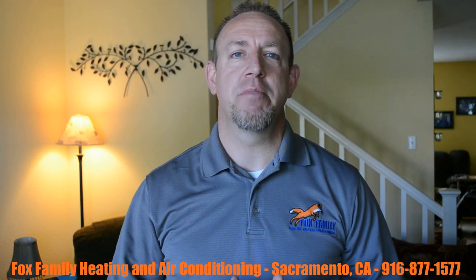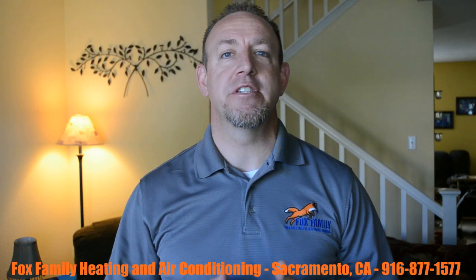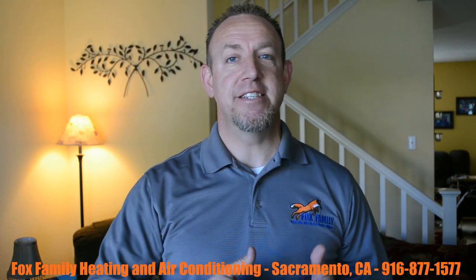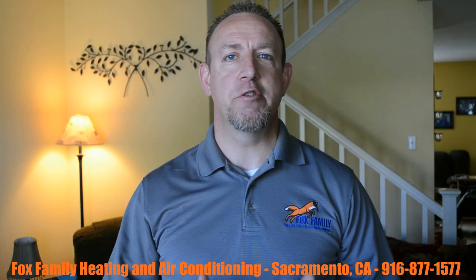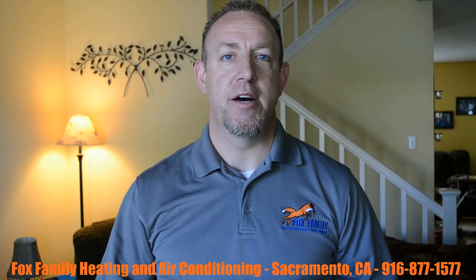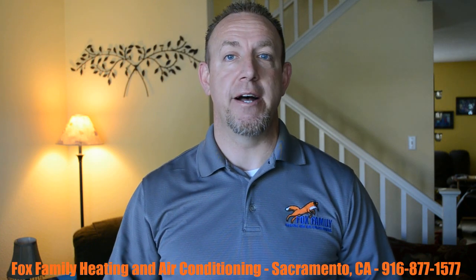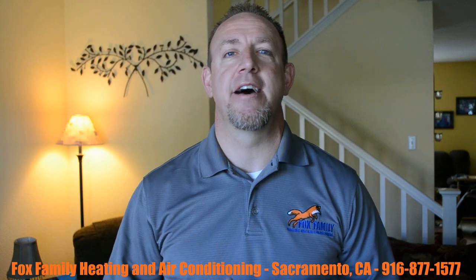One of the most common complaints I get as an air conditioning contractor in Sacramento is my AC is not running, or I can feel air coming through the registers, but it's not cold air. When I hear this, I usually start at the thermostat and determine whether it's set in the proper mode or cool. Next, I head out to the outdoor unit or the condenser to see if it's running or not. If it's not running, then I know that there's something going on with the AC outside, and that's where I focus my attention first.